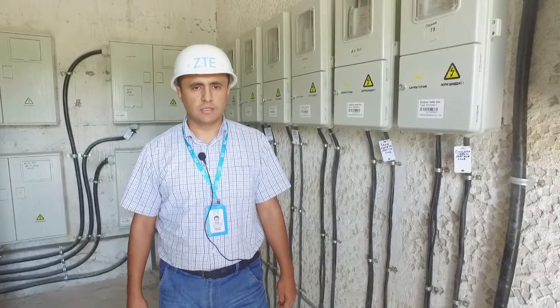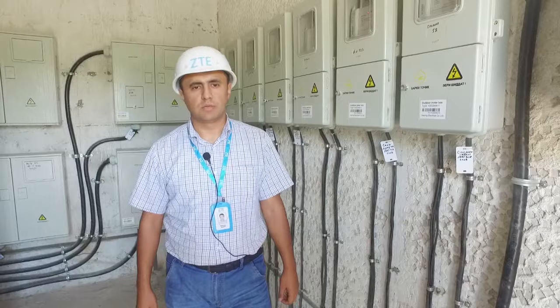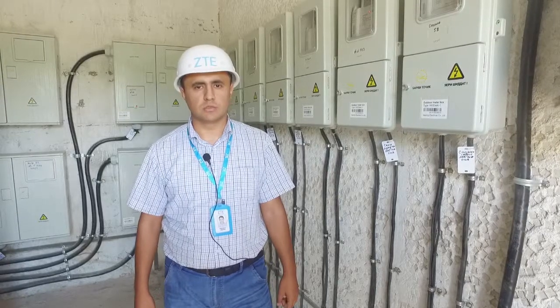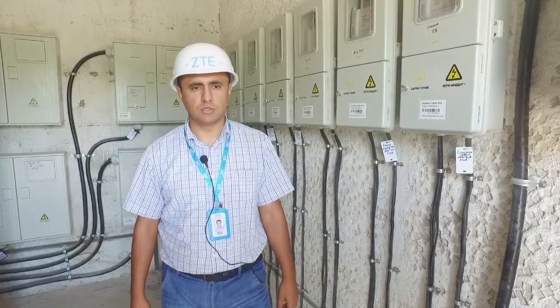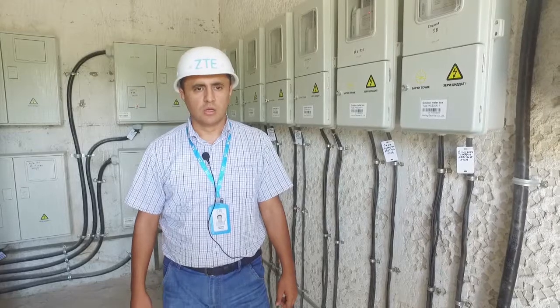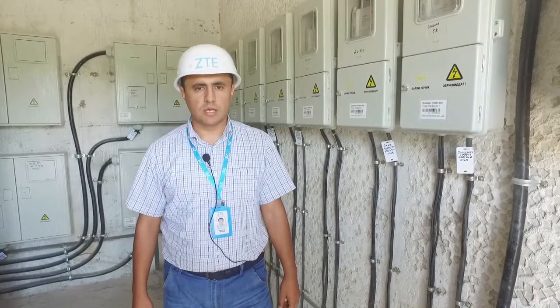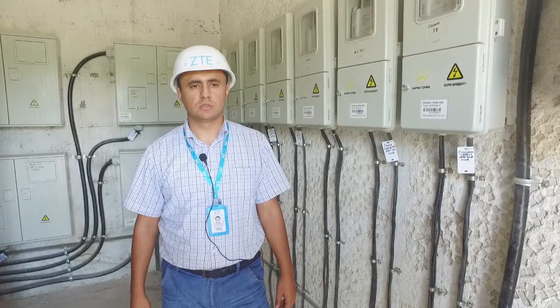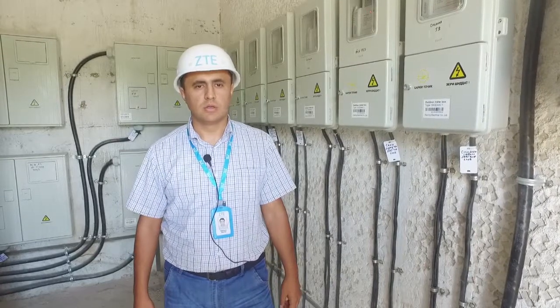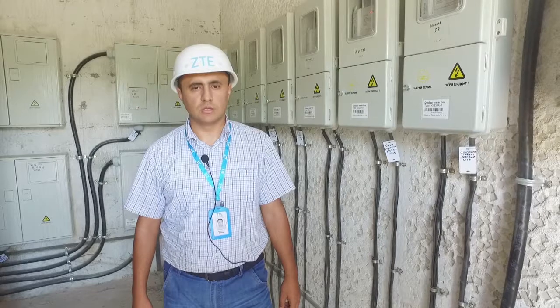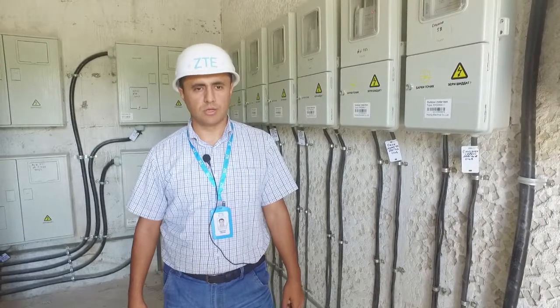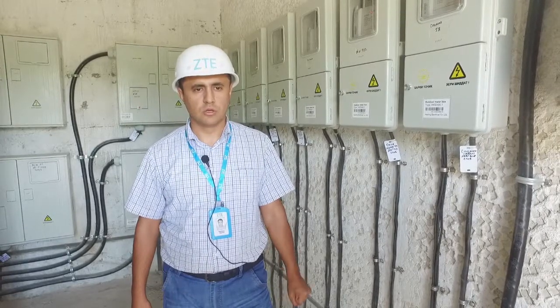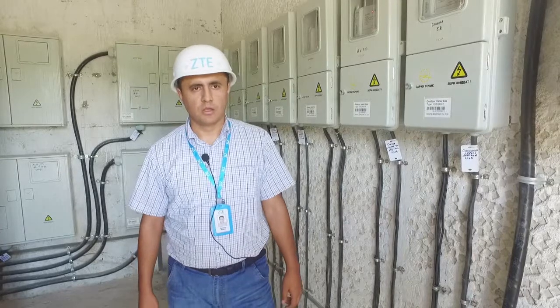Reading and signaling data transfer between meters and the data concentrator happens through PLC or GPRS technology. That is why our meter boxes have 2 options for interconnection between the data concentrator and meters. To make it happen, we can use a PLC collector or GPRS collector from meter box to meter box side.